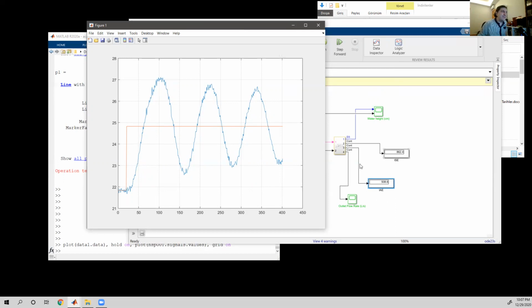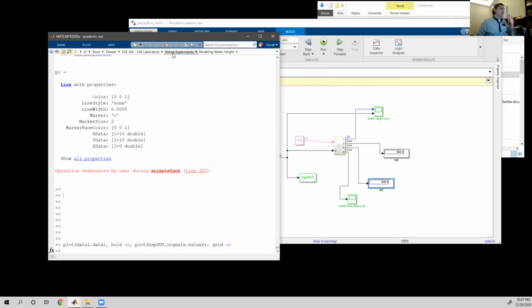Now, if these values are close to 0, or as you can lower them using process control, then it is deemed to be a better controller. But we are also going to use our visual assessment, and I'm going to talk about a couple more things, but I have connected these so that we can use them for assessment. Okay, so these values are awful. So what I'm going to do is change the Kc and tau I values, and this is a very typical response that we obtained from directly applying Cohen Coon settings.